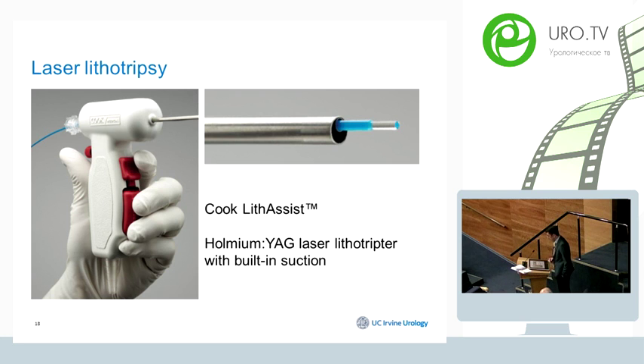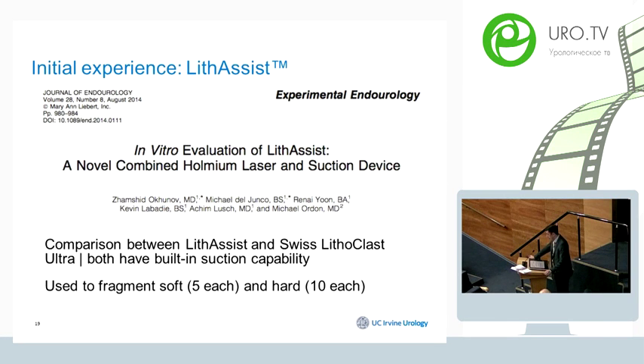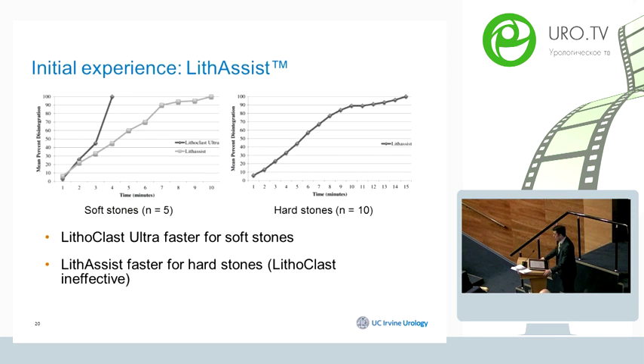LithAssist is a device designed in collaboration with Cook and our team at UC Irvine that combines a suction device with a laser device. We performed a small in-vitro study comparing LithAssist to Lithoclast Ultra, using gypsum stones — 5 soft stones for Lithoclast Ultra and 10 hard stones for LithAssist. For soft stones, Lithoclast Ultra was efficient at fragmentation and removal. However, for hard stones — equivalent to high-density, high-Hounsfield-unit stones — Lithoclast Ultra was not even able to fragment the stone, while LithAssist using 1000-micron laser fibers was really efficient by comparison.